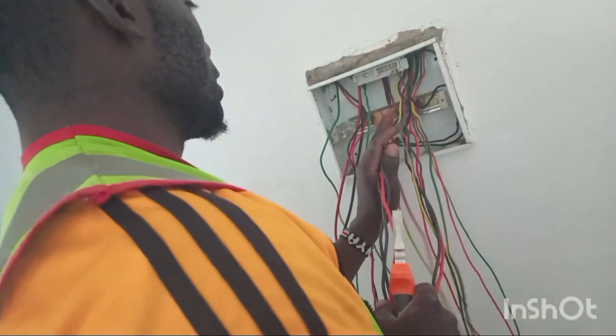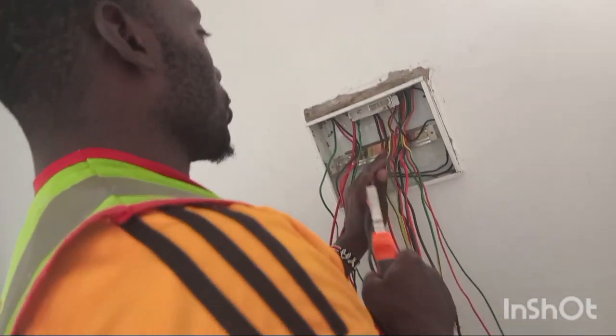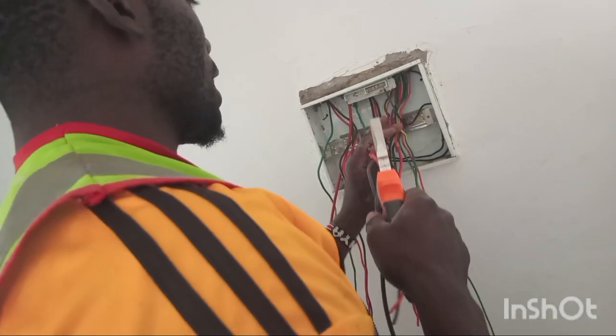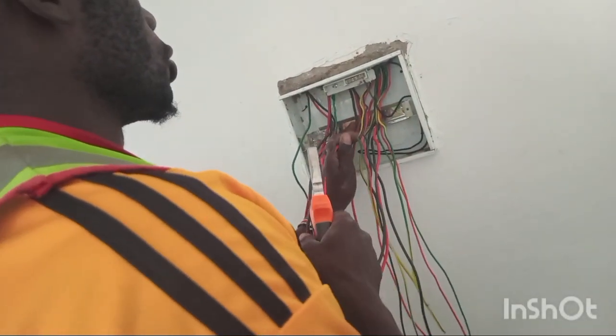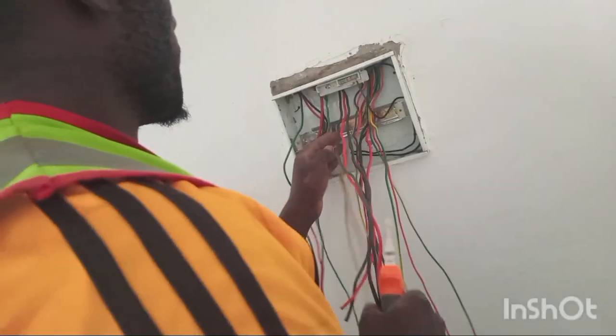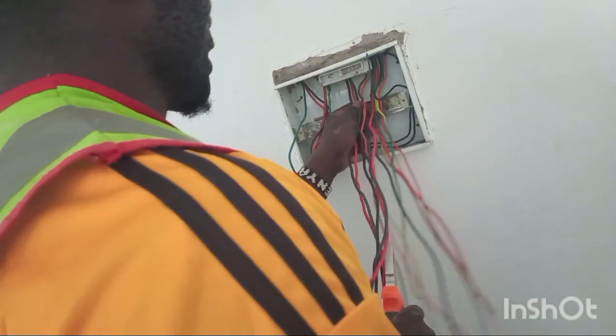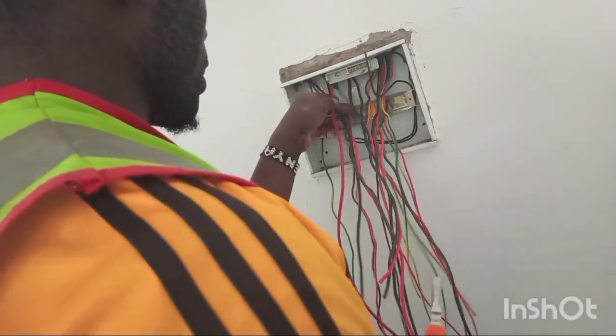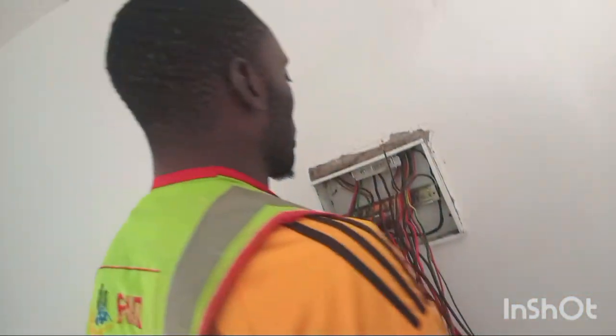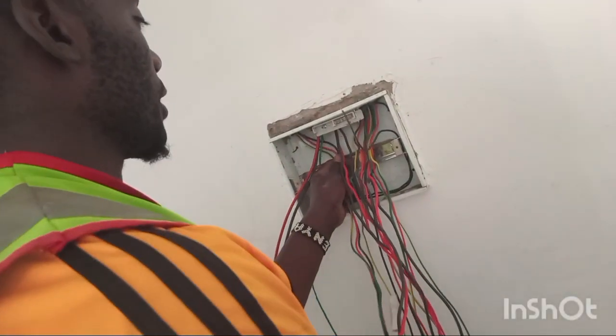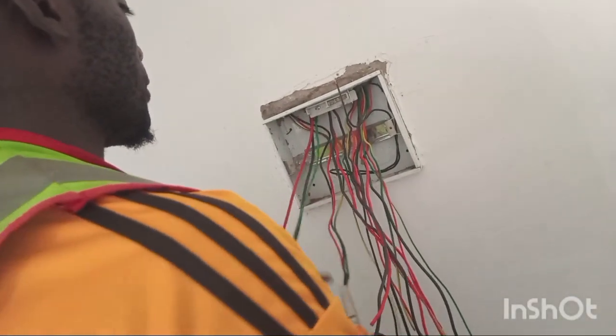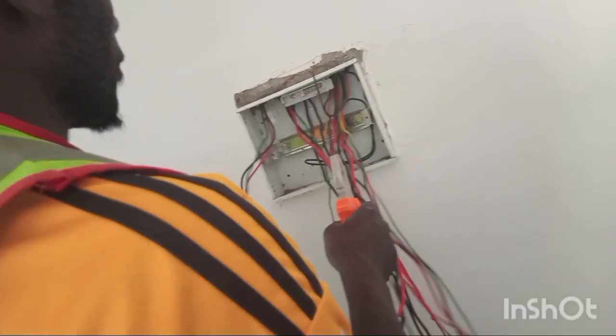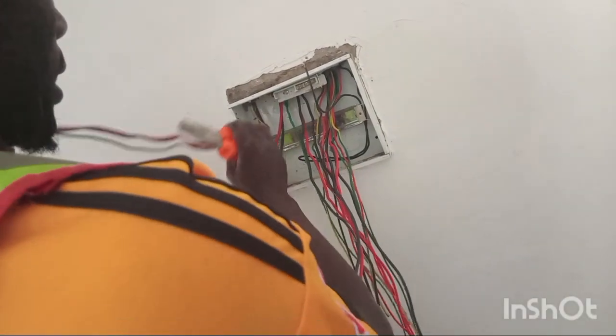So each washroom will be supplied with a 20 amp circuit breaker to control the system. Followed by the cooker, here we also have 6.0 mm cable, and we are going to use a 32 amp circuit breaker to control the cooker, so that in case of any fault, it finds an easy way to trip and save the life of our clients.